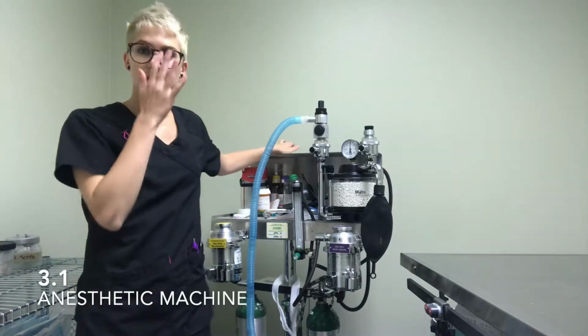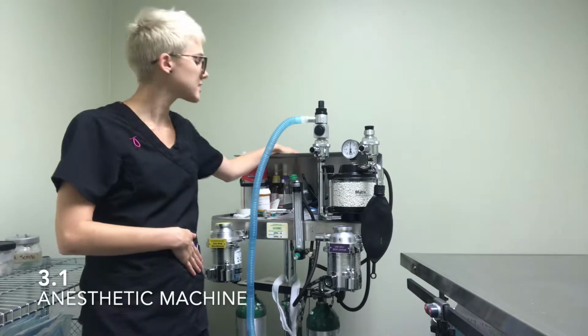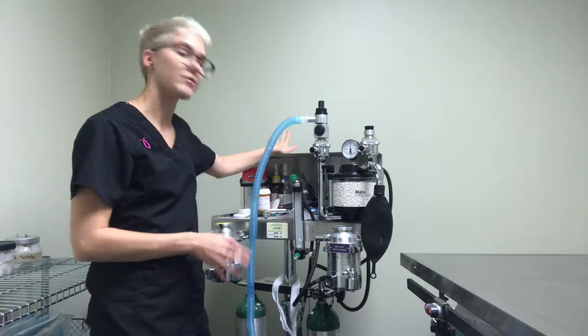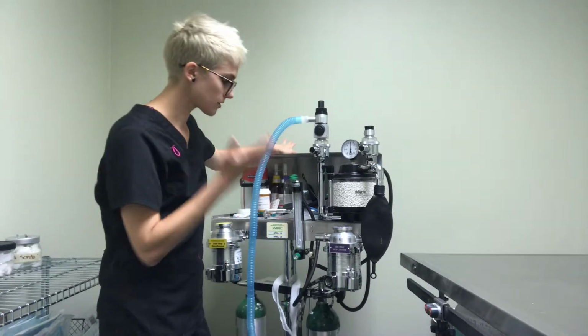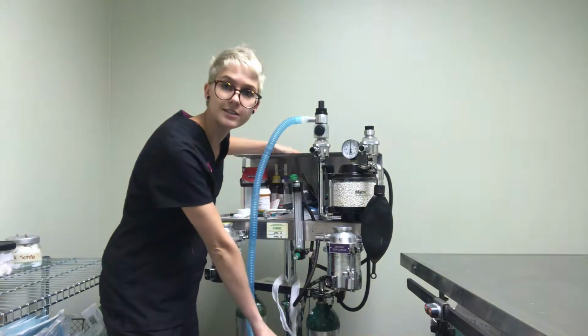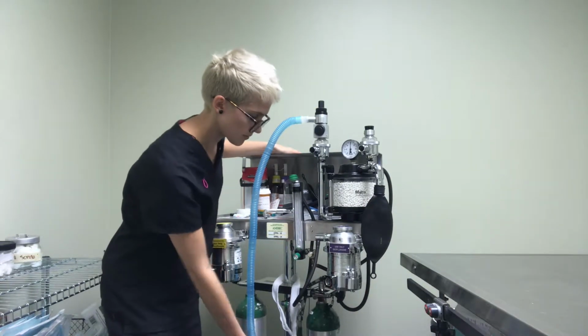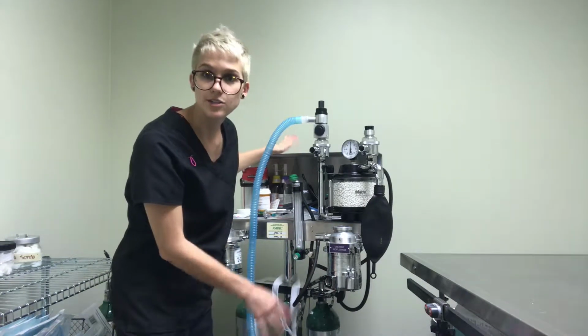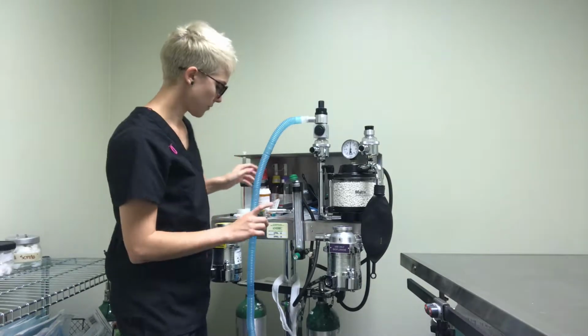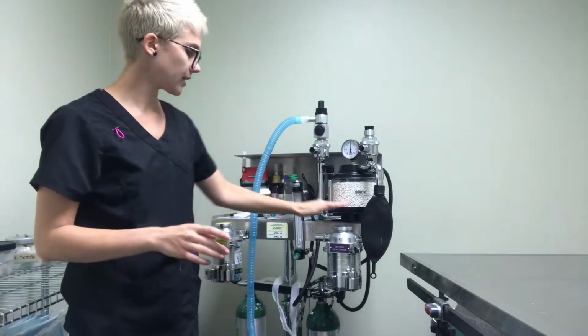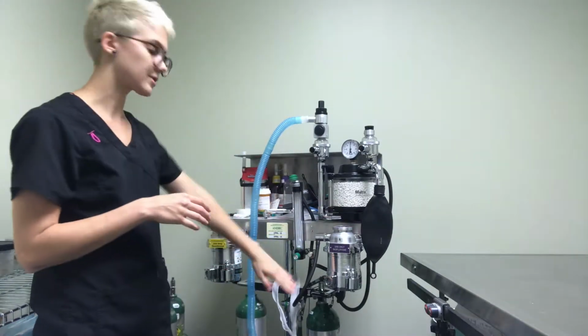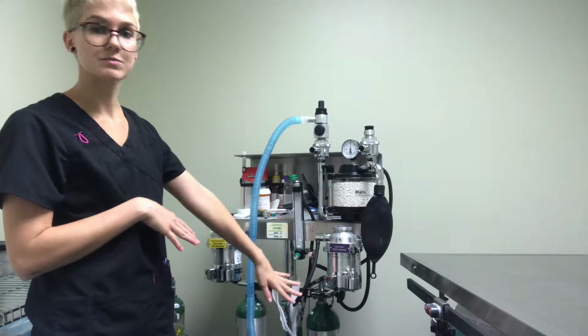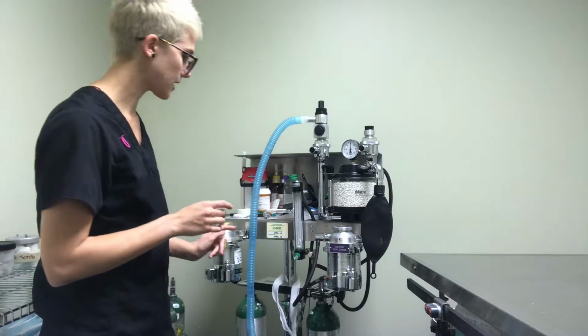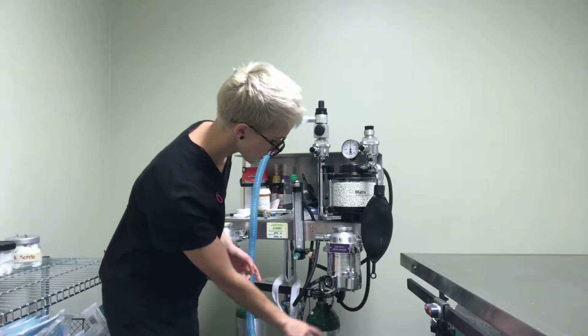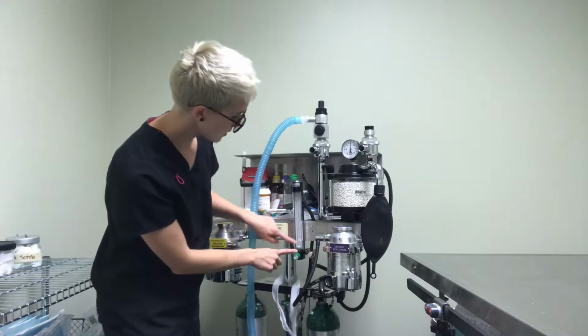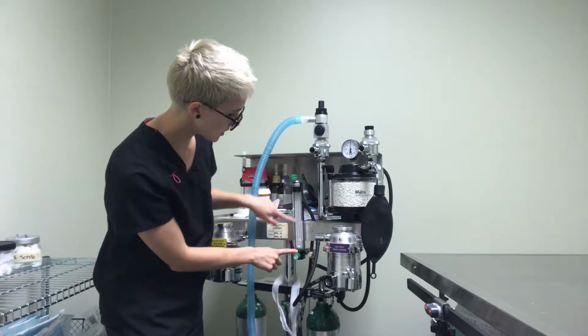Okay, so this is the anesthesia machine that we use in my practice, and I'm going to go over the parts of it. So starting at the bottom here, we have our oxygen tanks. They're going to supply the oxygen to the machine. We have a sevoflurane and an isoflurane vaporizer. Right now it's hooked up to the isoflurane, and that's what we use most, so I'm going to go through that side of it. Basically the oxygen is going to come out, and then you've got your flow meter.